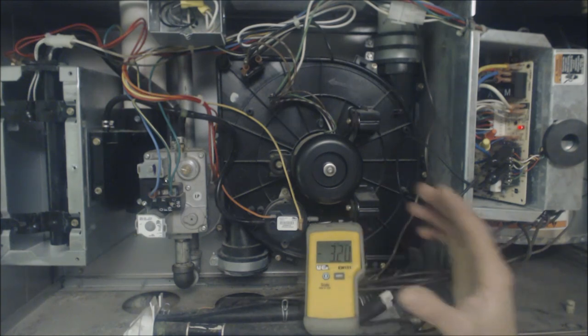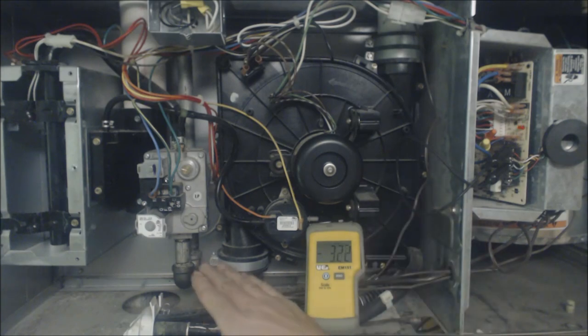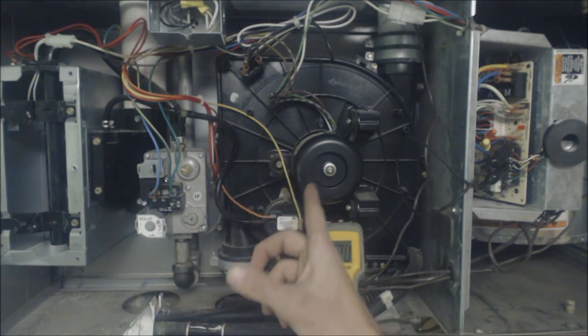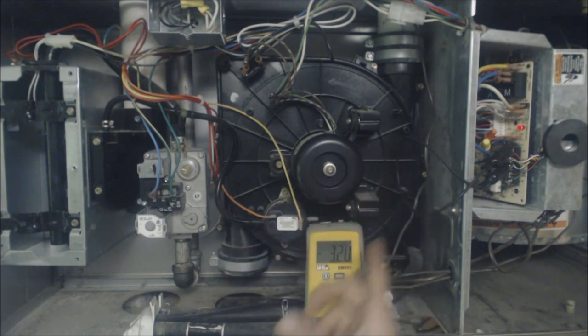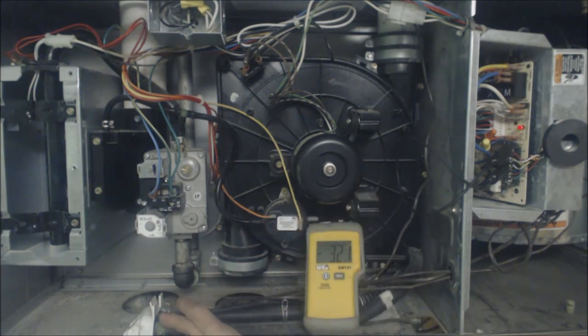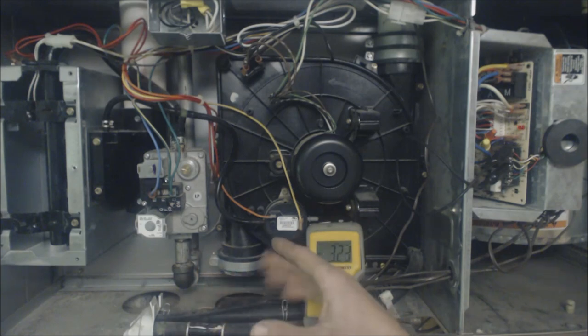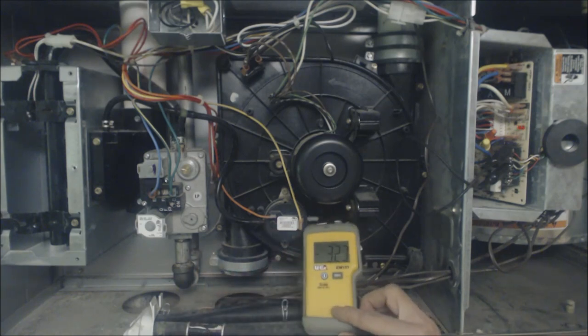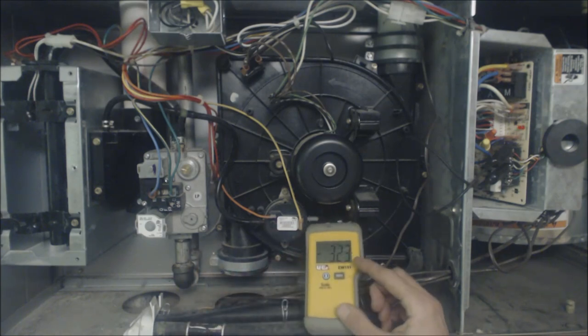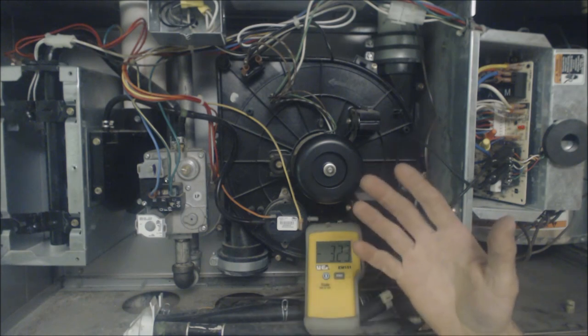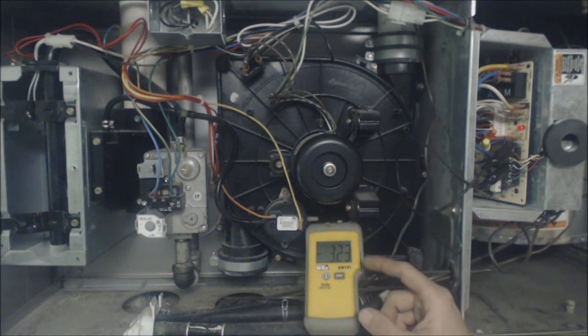I will tell you sometimes you're going to have an intermittent problem because of the water in these traps. So as the furnace is running it's creating water and it's coming into the trap, it's filling the trap up, backing up and then your water column reading is going off.